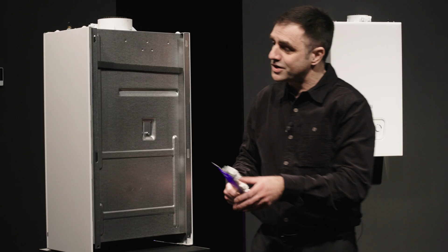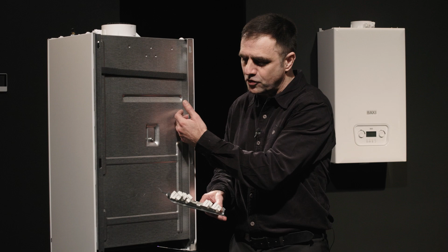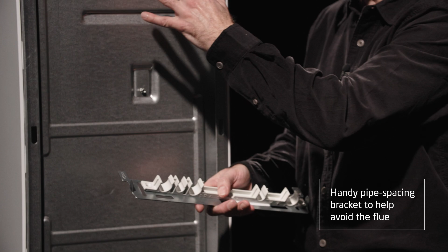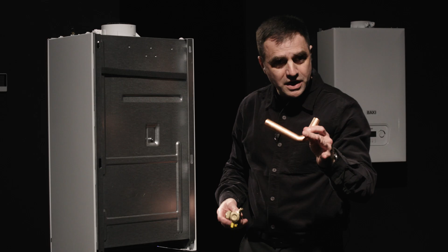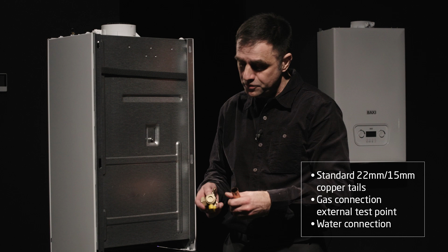And of course, if I want to put it in a kitchen cupboard but put pipes behind, I can do so with this boiler. I've got a nice little handy void in here. I'm going to get my hanging bracket, obviously, but what I also get is this pipe spacing bracket, and it's going to sit behind the boiler, and it's going to put the pipes in the right position to avoid the flue if you're going out rear flue. Also, you get copper tails in the kit, and they can go down or upwards. Standard 22mm or 15mm, so you don't have to use the tails. You can use standard copper if you want to.